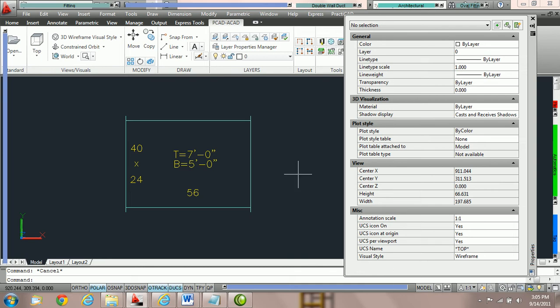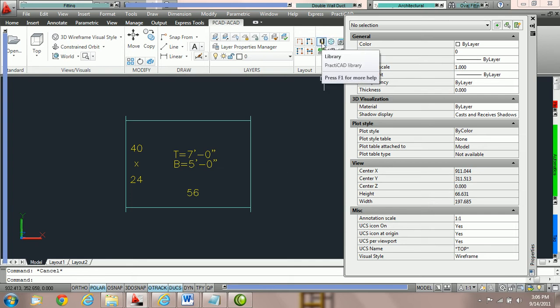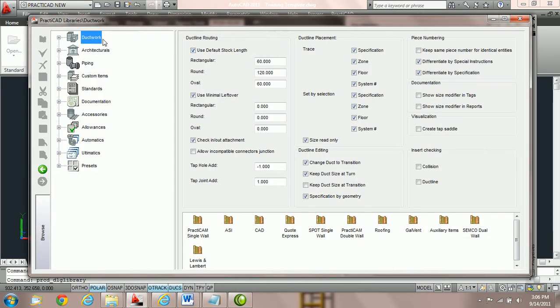Label only means first we should send this fitting to a sheet shear list or download it to a coil line, and second it means it should follow the default stock options selected in your library ductwork options. To show you where that is, we click on Library and then Ductwork. Notice here we have 'use default stock length' checked and for rectangle we have 60 inches. If you choose label only, PractiCAD will ensure that as you change connections, the finished length meets this stock length.